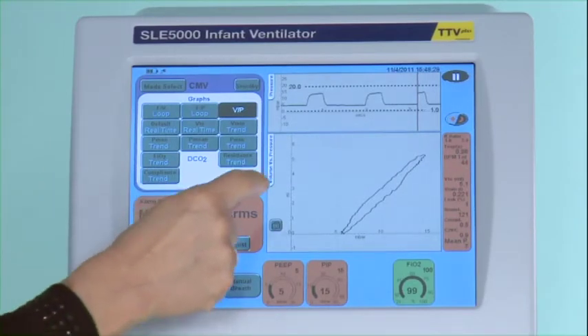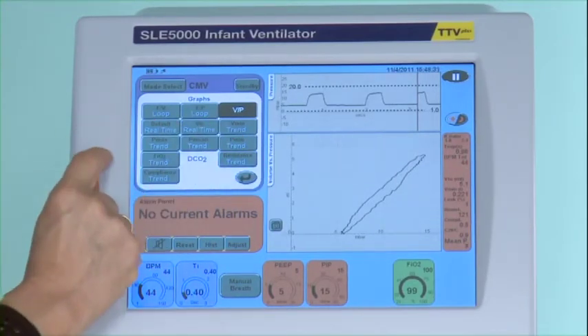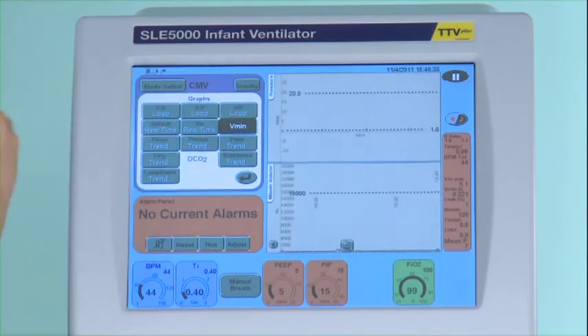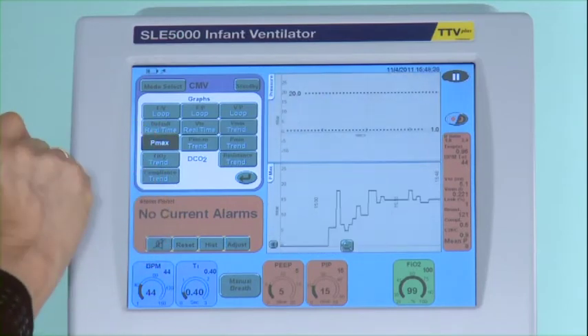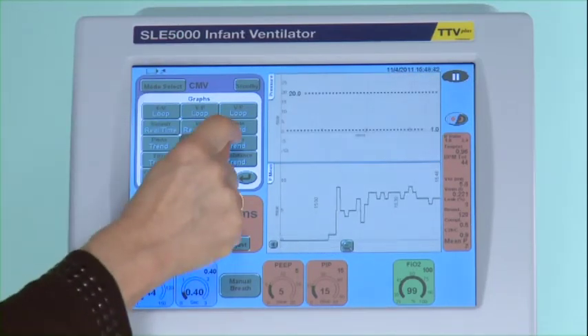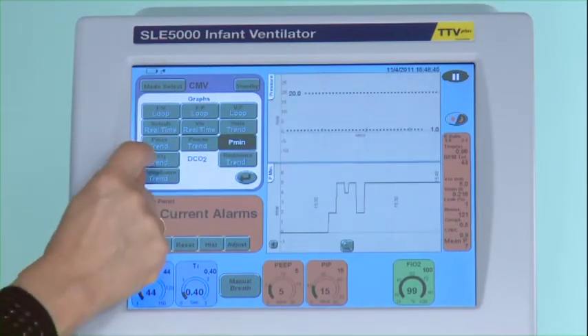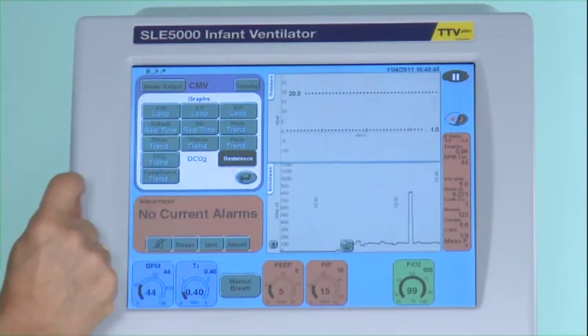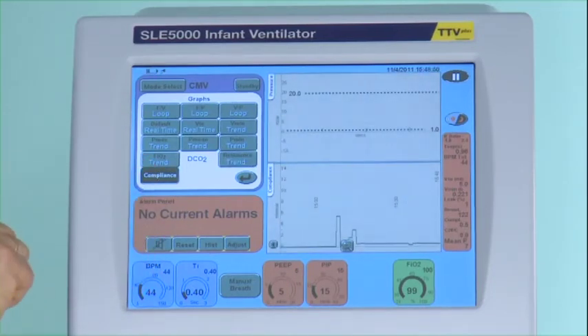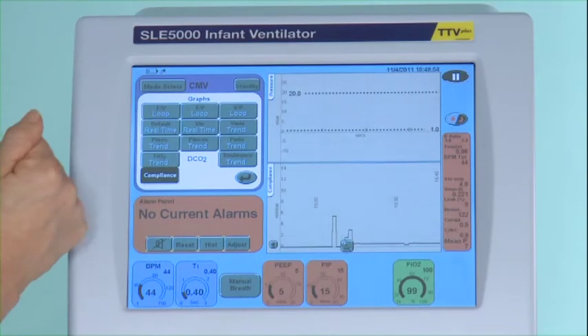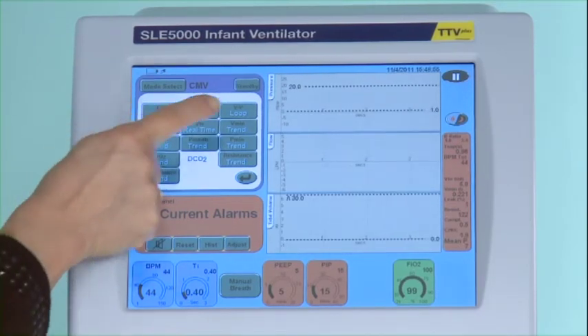You can also trend on any measured parameter over a 24 hour period. Available parameters include minute volume, positive end expiratory pressure, mean airway pressure, peak inspired pressure, FiO2, and resistance and compliance. If you don't want to look at any of these you go back to default, you get your three screens back and the arrow brings the icon back.